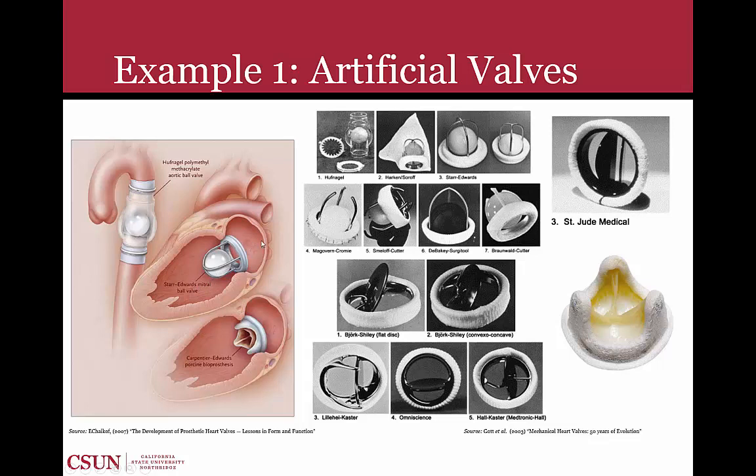The problem again is that you still have a slamming of the ball on the orifice, so that's going to cause blood damage on the outer edge of this seat here. So while it was less invasive in the sense of implanting this device, you still have problems of blood clotting and blood damage due to this.